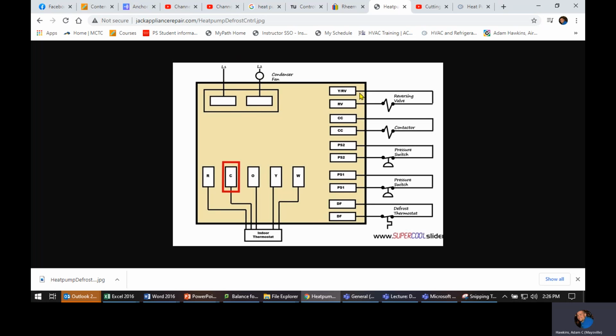You'll also notice that the reversing valve is running off of that. Reversing valve is going to have a common on it, and then it's going to have an orange or a signal wire. So this board will get power in on orange, saying that the stat is telling it that it's in whatever position. And then that board, through its internal circuit, then sends that power to the reversing valve when it needs it, kills it when it doesn't. So when the board senses that it needs to go into defrost, the thermostat doesn't know anything about it. The thermostat is completely out of the loop on this. All that the stat knows is that it needs heat and it's calling for it. This unit, this board, is doing its own thing to try to keep the outdoor unit happy.